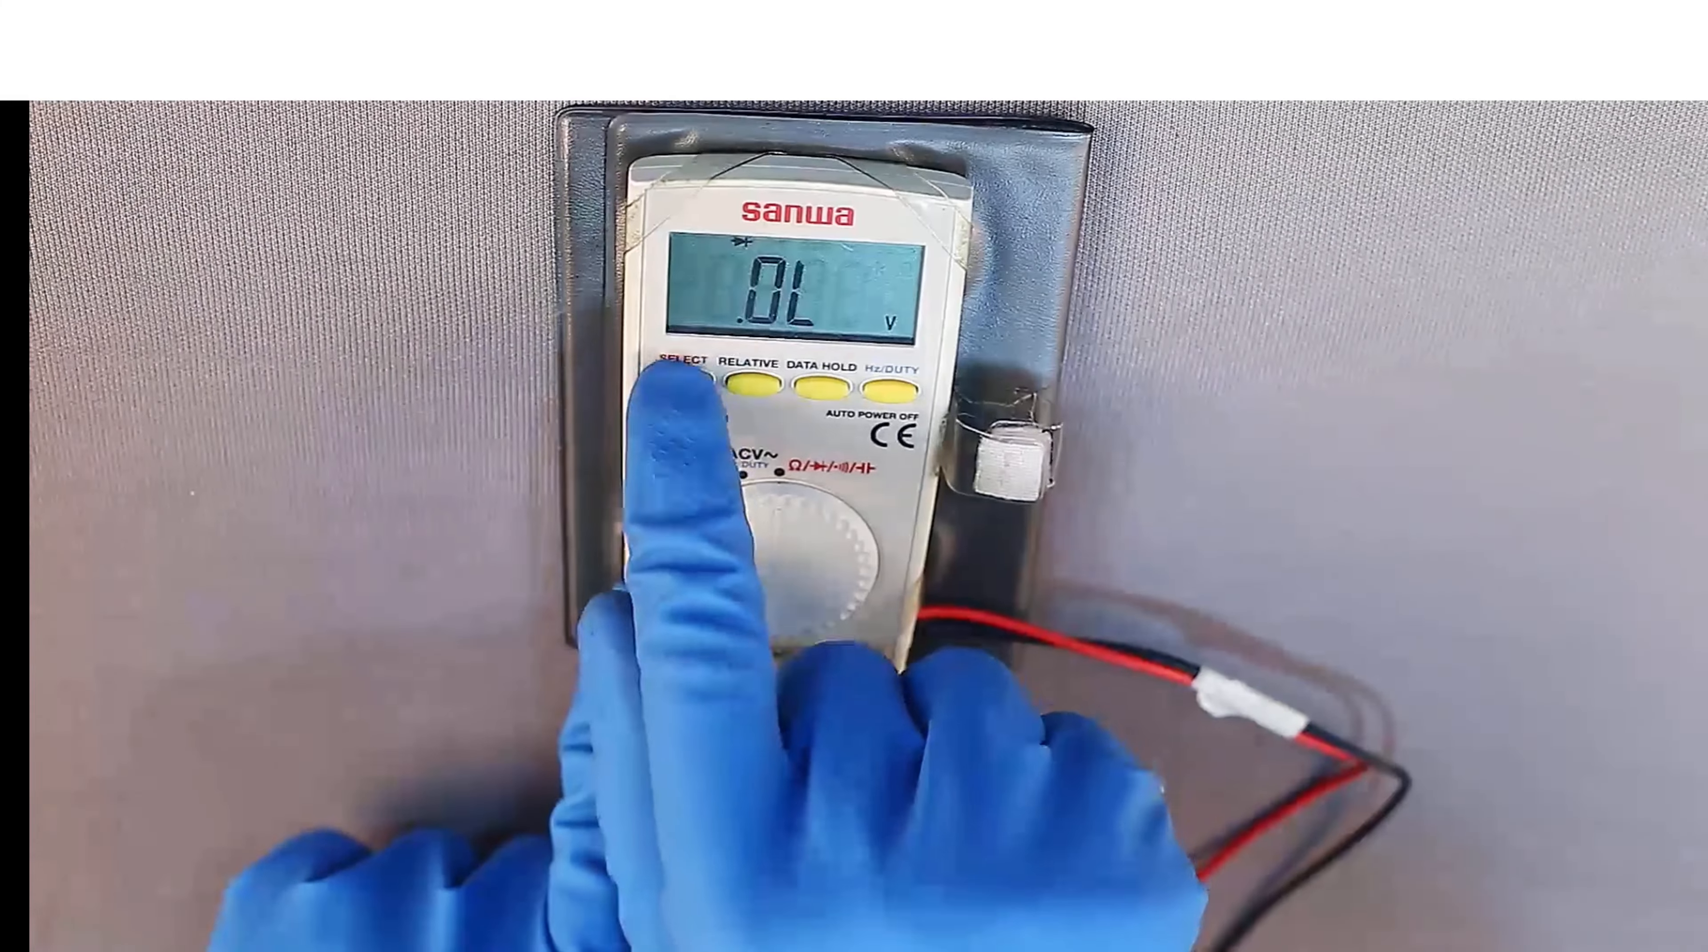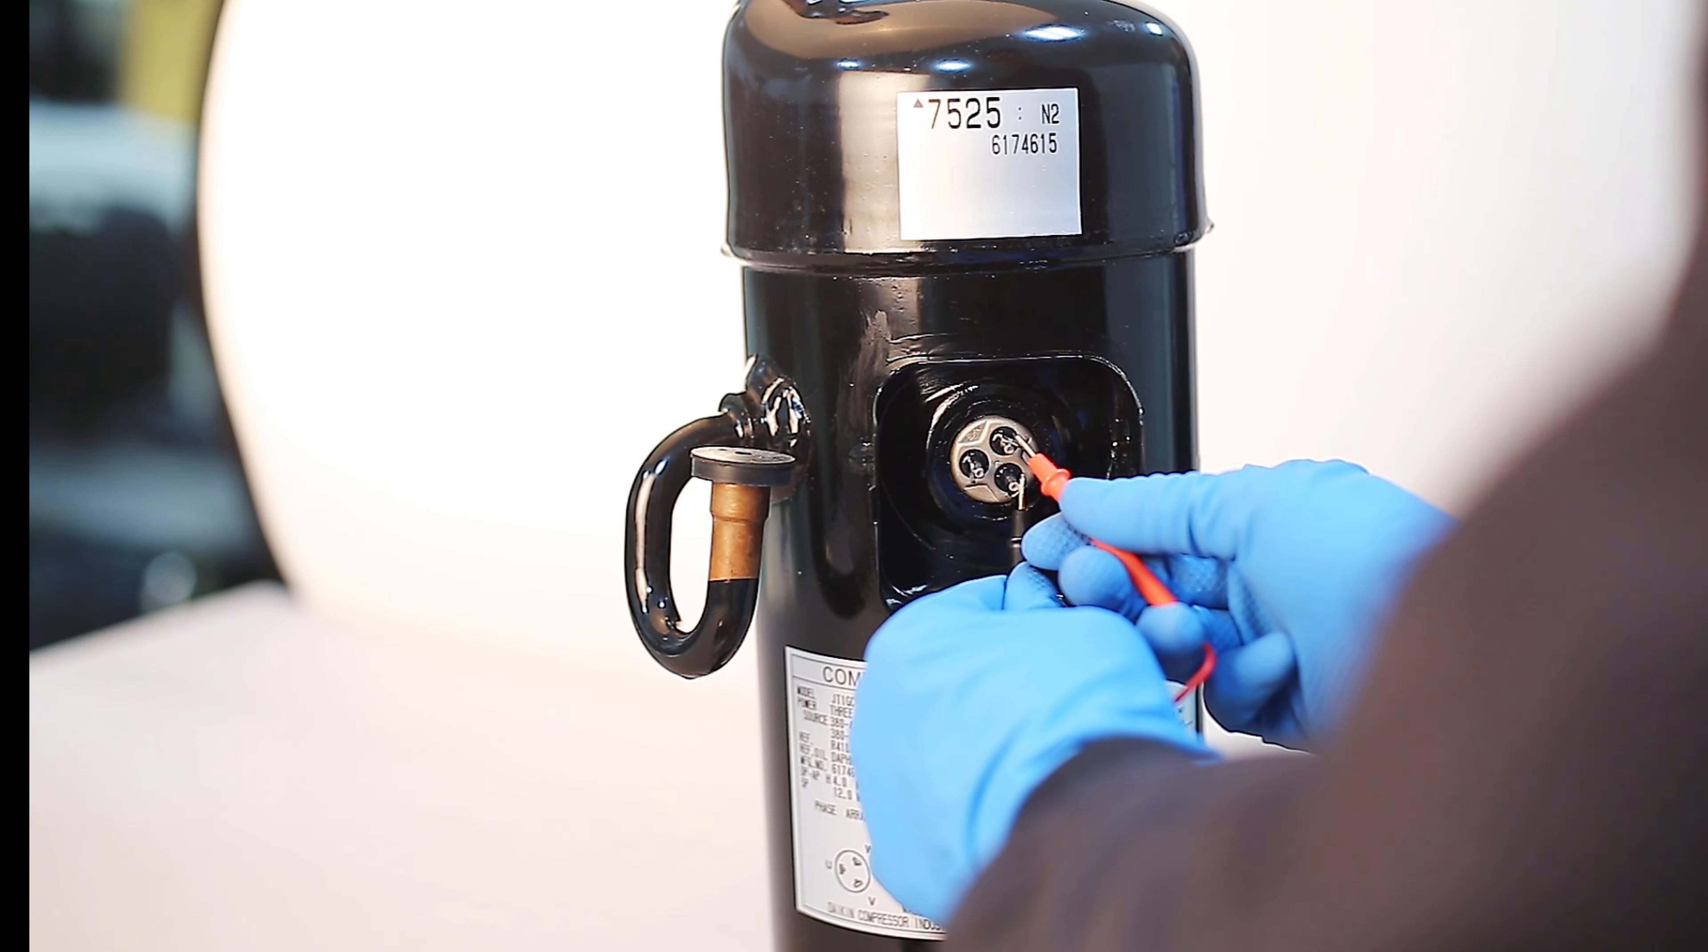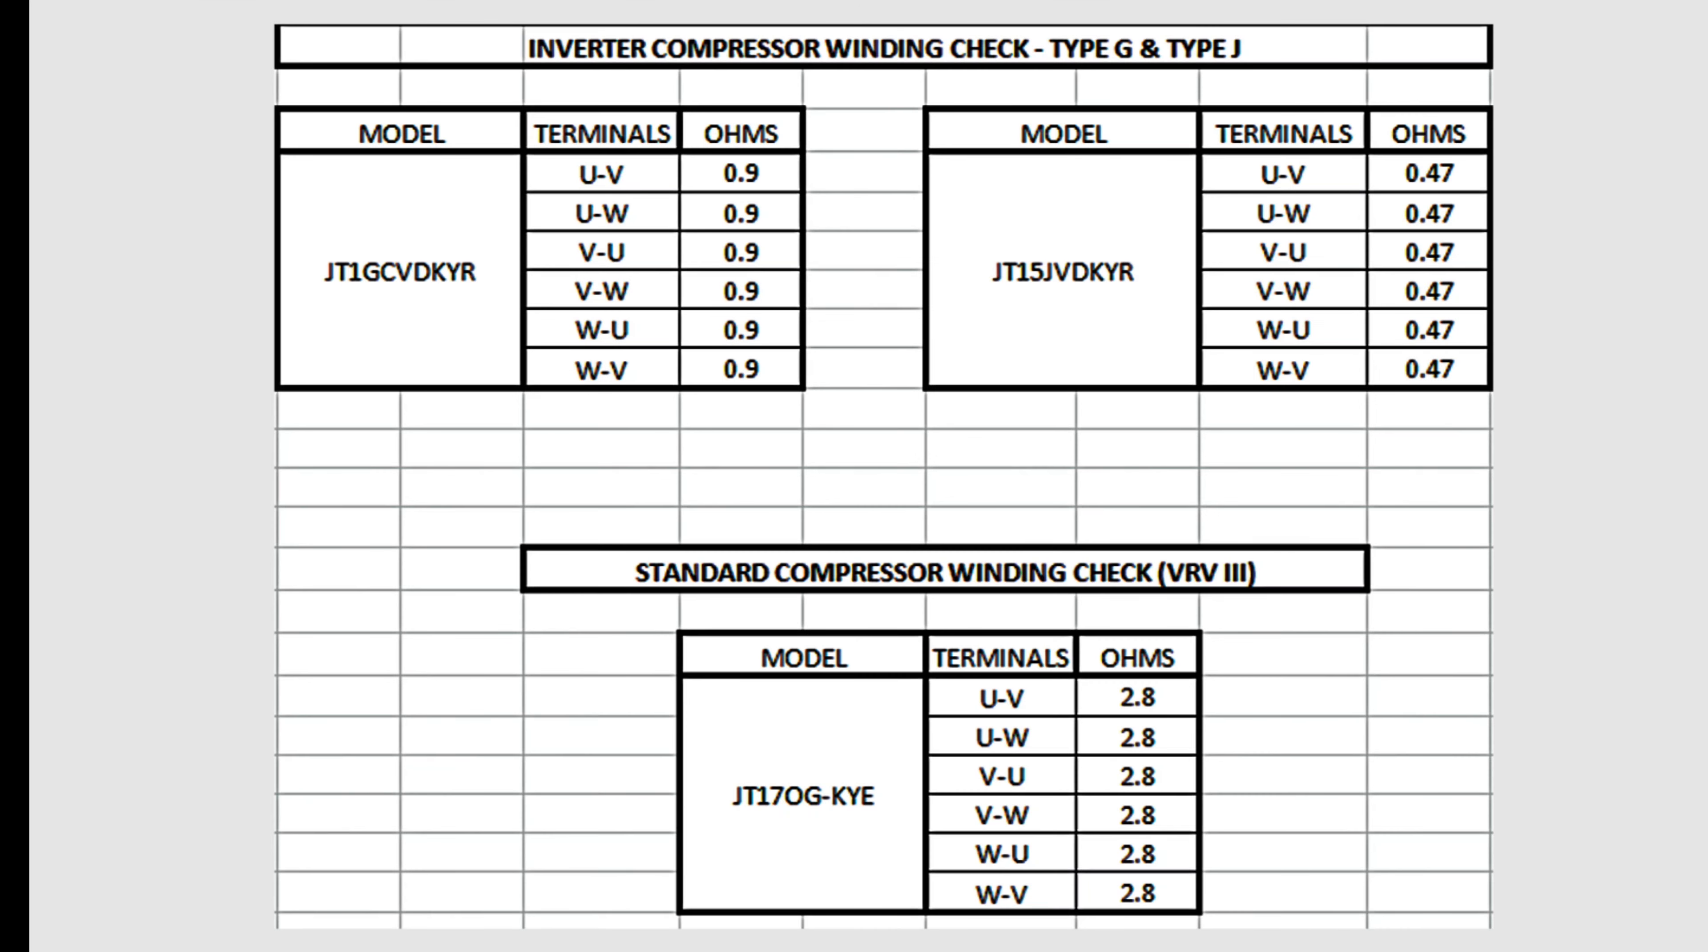Now set the multimeter to resistance mode and check the resistance between U and V, U and W, and V and W one by one. The resistance value of all three checks should be as per reference value based on the compressor model, plus or minus 10 percent. The check sheet for this test is shown on the screen.